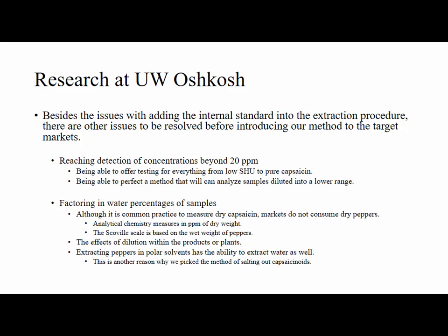All right, so besides the issue of adding the internal standard to the extraction procedure, there are a couple other issues that would need to be solved before releasing this to our target markets. One of them would be reaching concentrations beyond 20 ppm if we wanted to increase the limits of our instrument. This way we'd be able to offer testing for everything from low SHU, being your bell peppers, to pure capsaicin, being peppers like the Carolina Reaper.